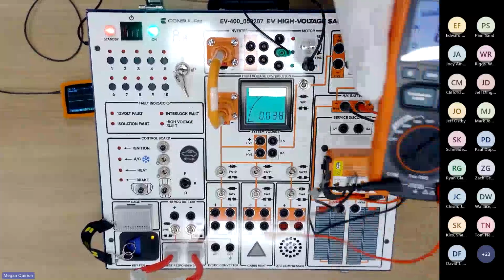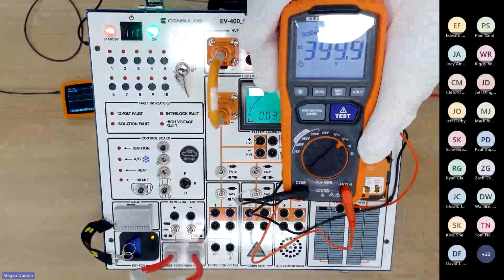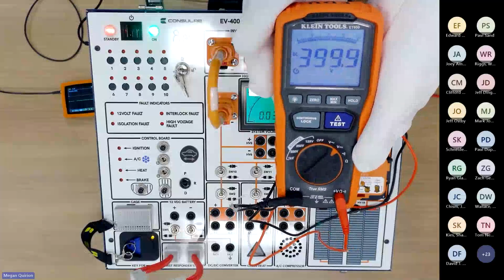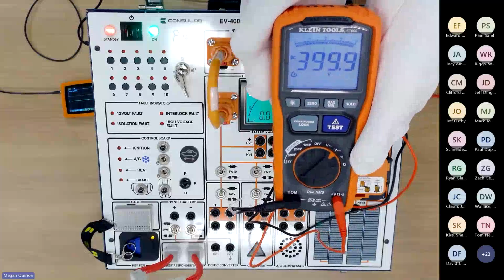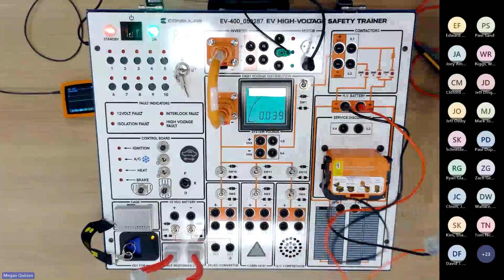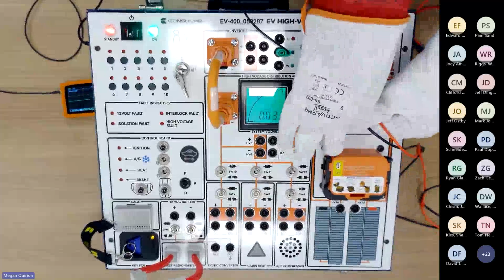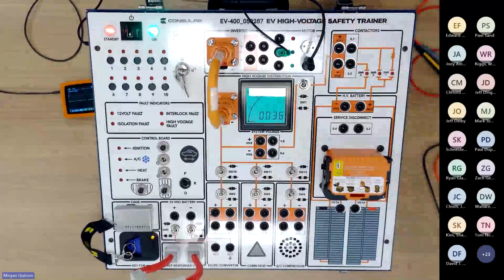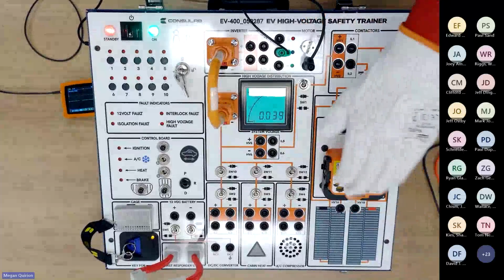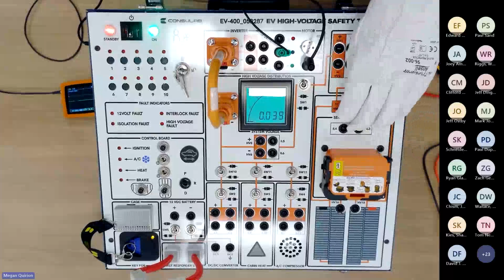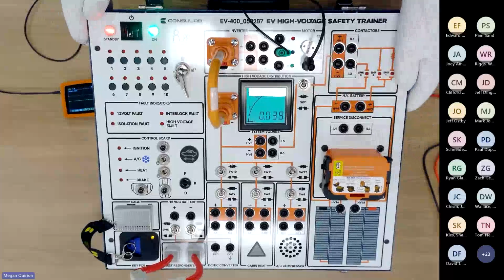So once again, the purpose of the service disconnect tool is to shut down the contactors to ensure no power goes to the components during servicing. But it does not eliminate the high voltage from the battery. The battery is still retaining 400 volts of energy within the module itself, going into the pre-contactors.